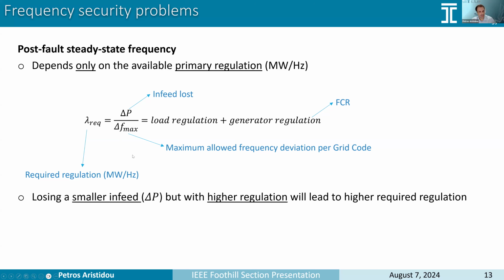Again, the same comment as previously. The largest in-feed loss is not always the worst case scenario. We could lose a generator that does not generate a lot of power, but provides a lot of regulation, a lot of frequency containment reserves, and that could be a worst case scenario rather than losing a higher in-feed power.